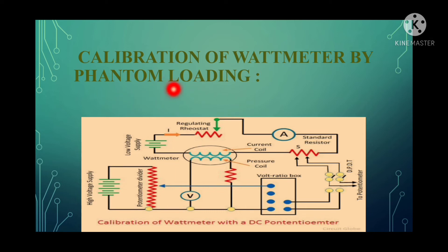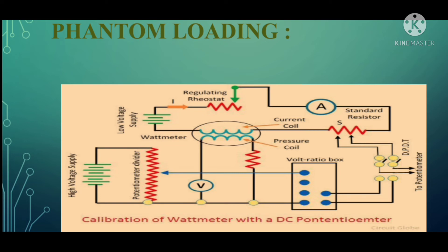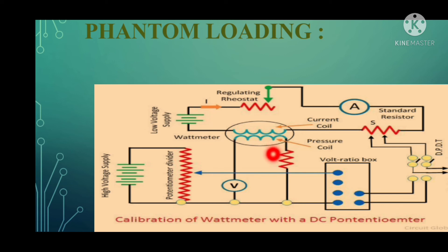Phantom loading is nothing but virtual loading. In the phantom loading arrangement, we provide a virtual load so that the power consumption is reduced and the loading effect is reduced. Since the current coil has a low value of resistance, we connect a separate low voltage source to supply the current coil. An adjustable rheostat and a standard resistor are connected to the current coil side. On the pressure coil side, we connect a high voltage supply, because the pressure coil always has a higher value of resistance.